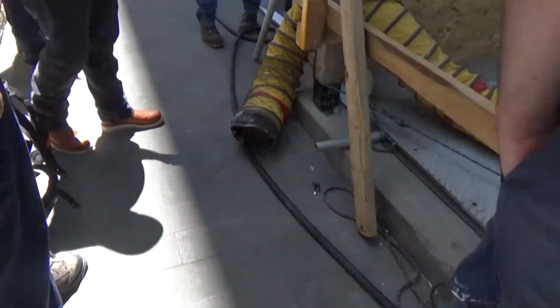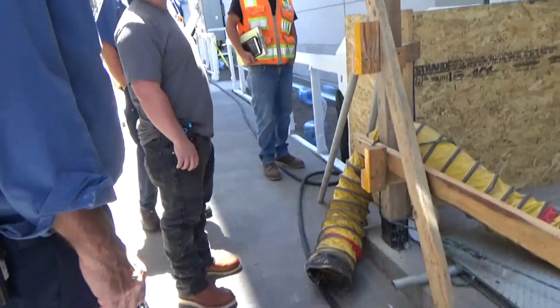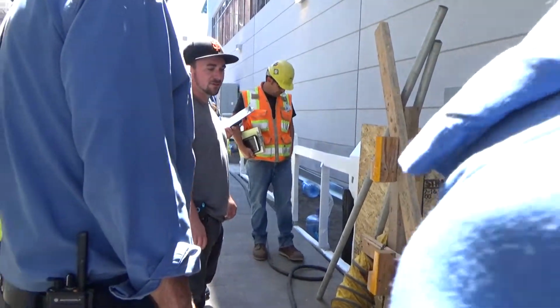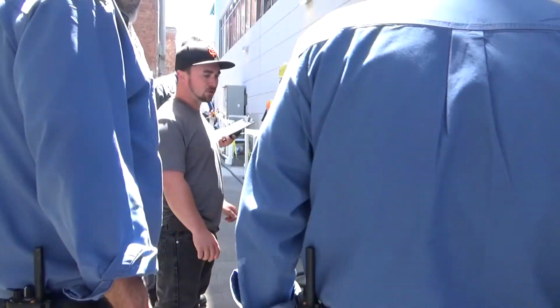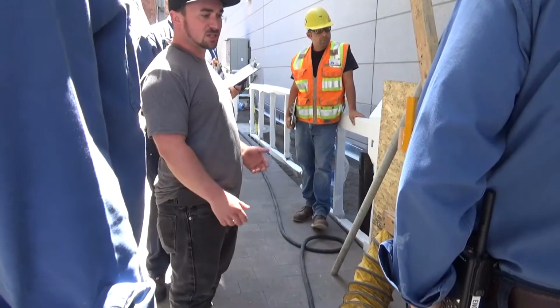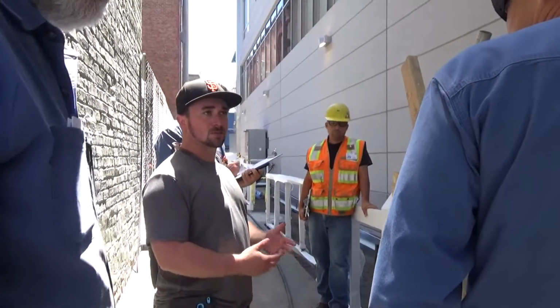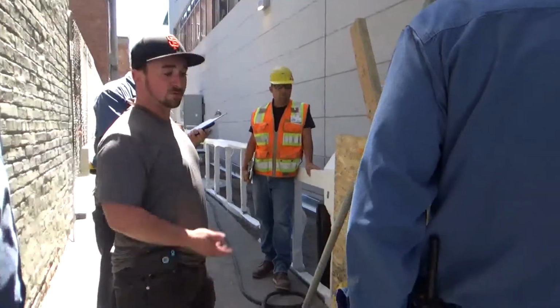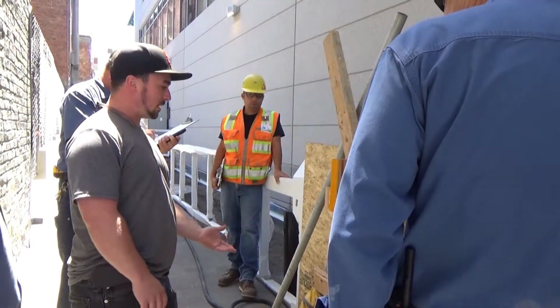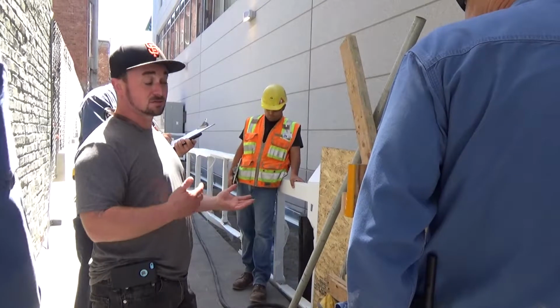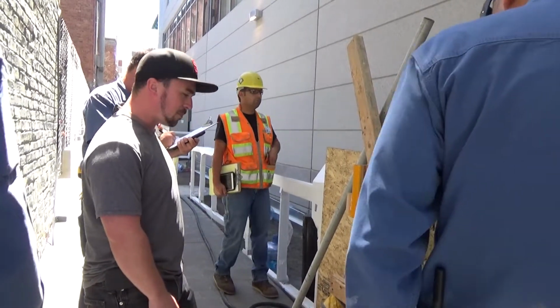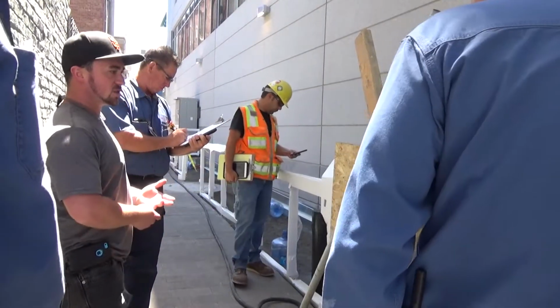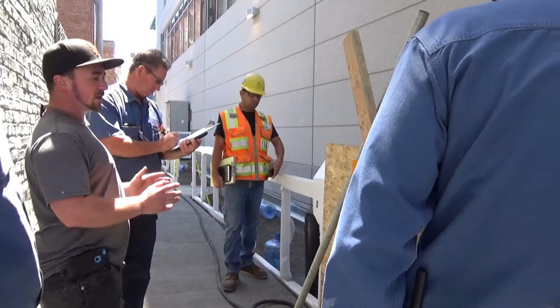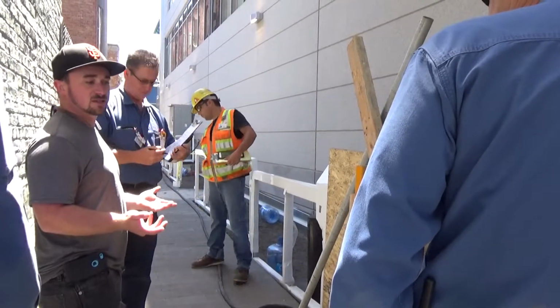Okay, so these are considered Weil systems. Weil is the manufacturer of the pump and the control panel. Pretty much, it's a duplex system. So it's two pumps in a pit, and you have 4 floats in there, and depending on which float makes, a certain sequence happens. The bottom float is pretty much just the on. Nothing happens, but the panel is energized in a way.